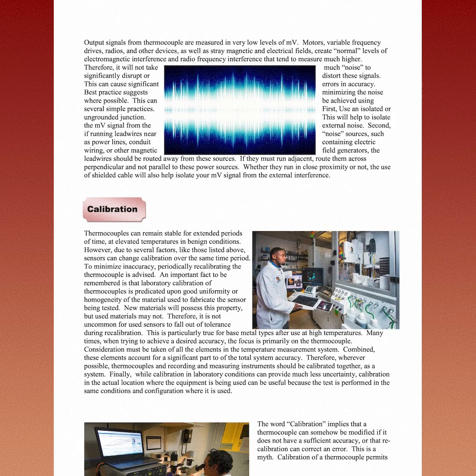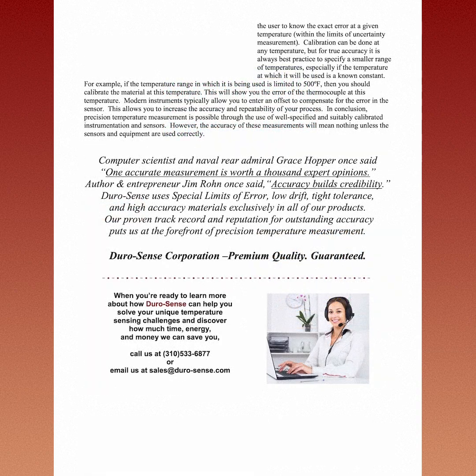The word calibration implies that a thermocouple can somehow be modified if it does not have a sufficient accuracy, or that recalibration can correct an error. This is a myth. Calibration of a thermocouple permits the user to know the exact error at a given temperature within the limits of measurement uncertainty. Calibration can be done at any temperature, but for true accuracy, it is always best practice to specify a smaller range of temperatures, especially if the temperature at which it will be used is a known constant.